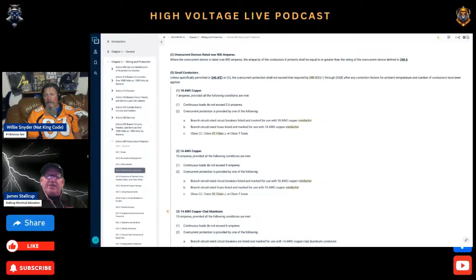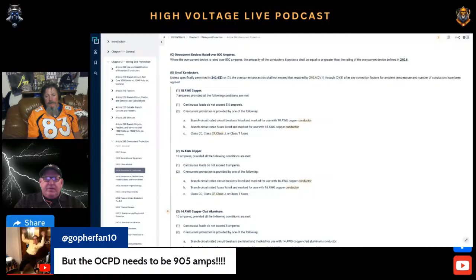True. I understand you're saying you have to protect the load, but you have to remember there's a lot of diversity built into those loads. Not all those loads are going to be operating at the same time. In other words, your service isn't going to be pulling 900 amps at all times. That just isn't going to happen. Dude, the overcurrent device does not need to be... Oh, wait, I was on the wrong one. The overcurrent device does not need to be 905 amps.